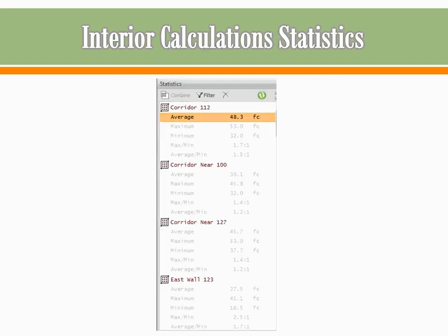So at that point, we can go ahead into the software itself, and it lays it out specifically so that we know how many foot candles we need on average, trying to average it so we don't have too low of a minimum and too high of a maximum at opposite ends of the room, to make sure that everything comes out looking nice, not too bright on the eye. So we drop those in there and then put them back in. Then we can go ahead and run the calculations so we know exactly what we're getting.